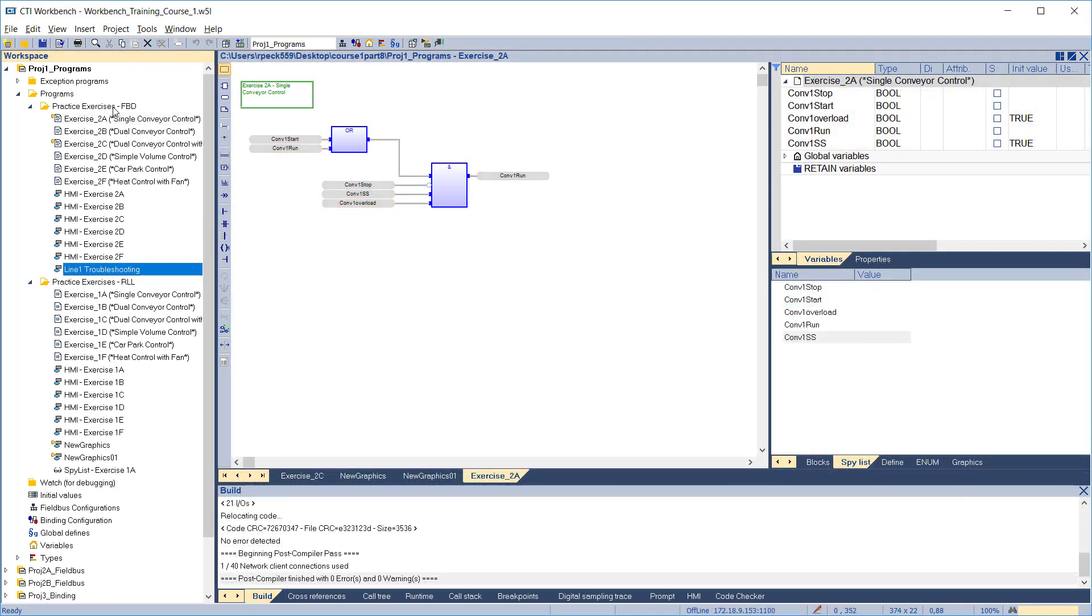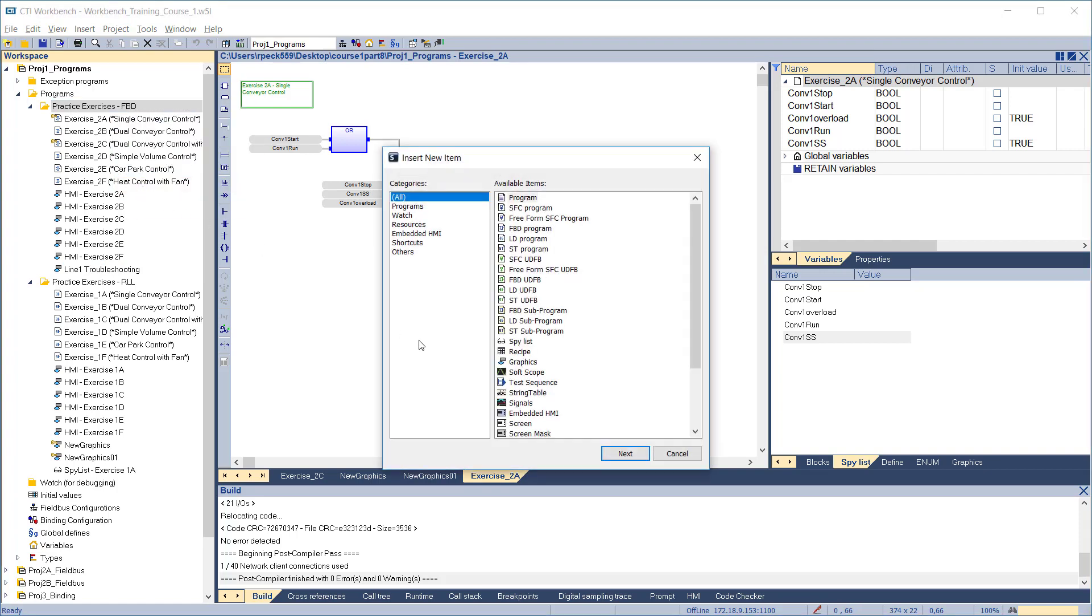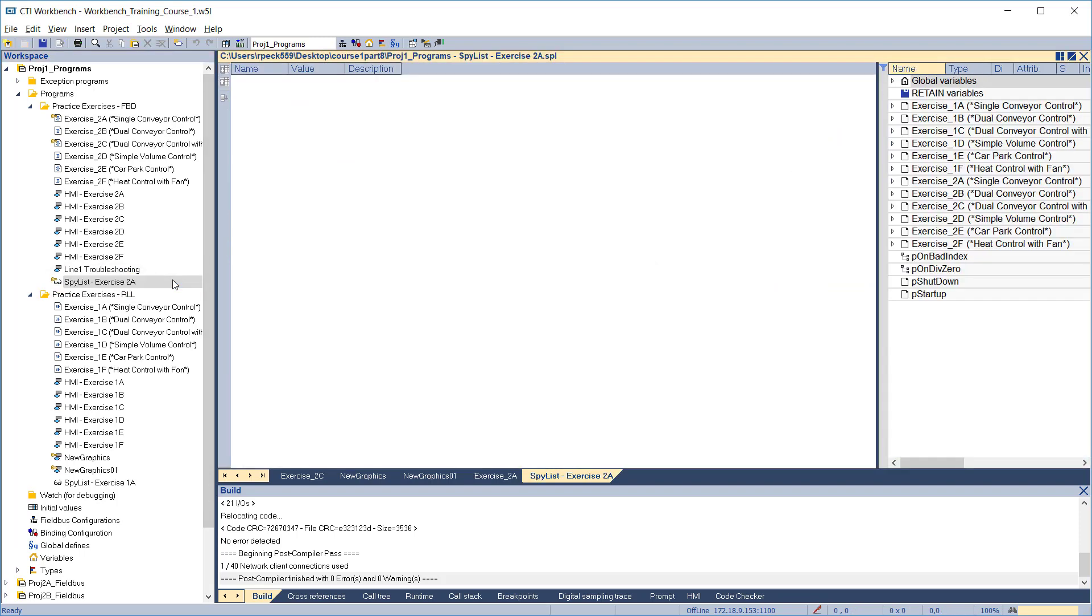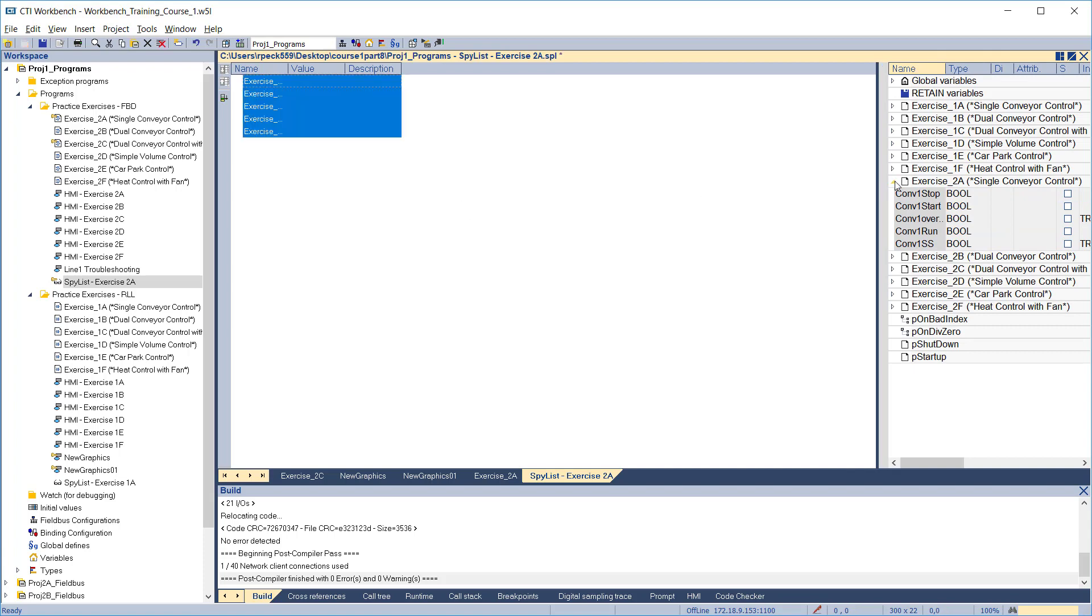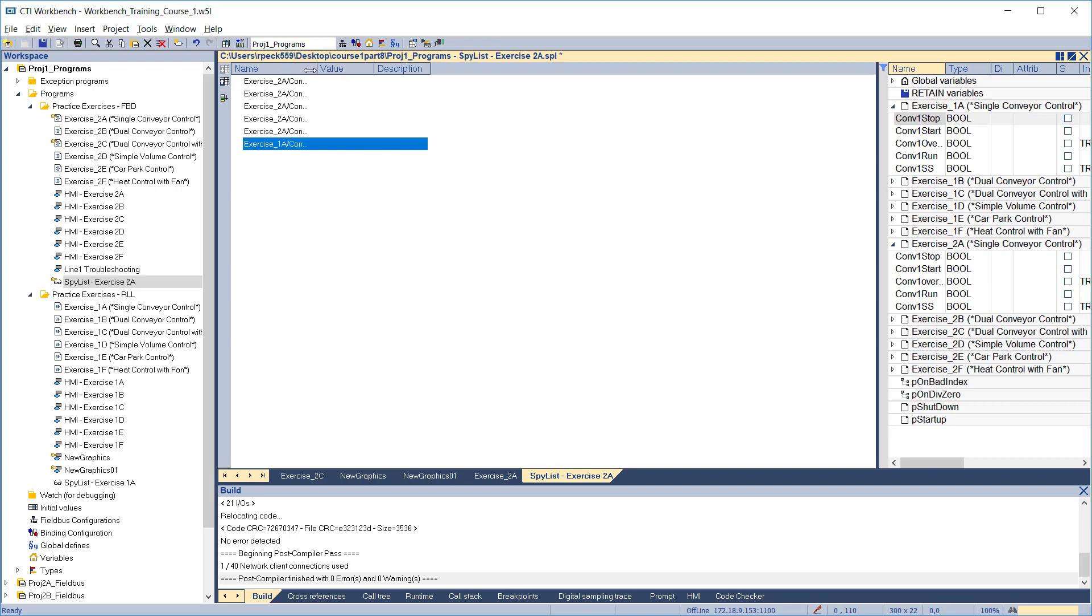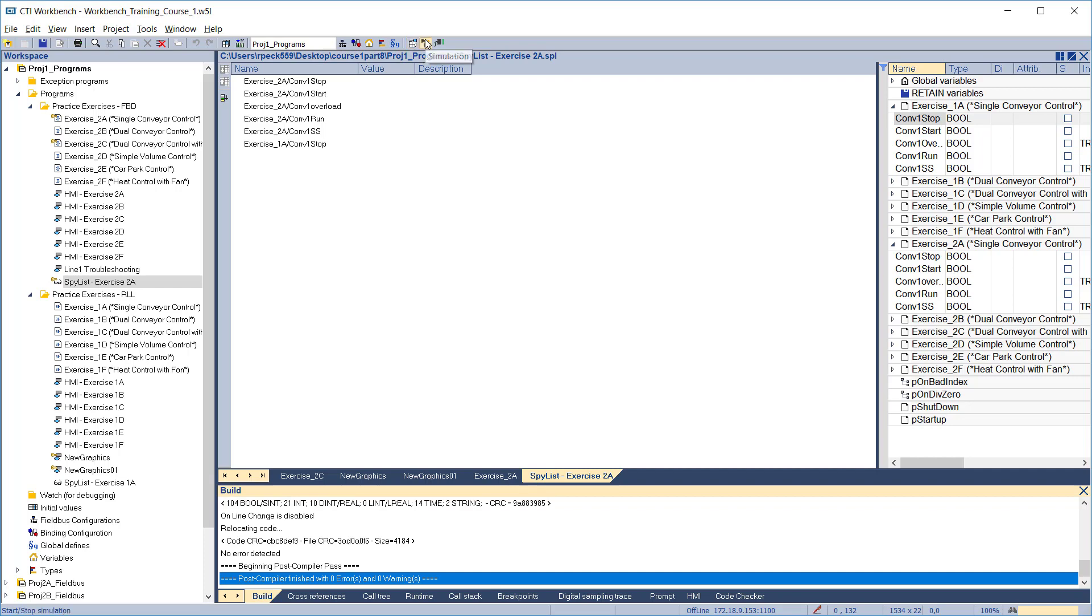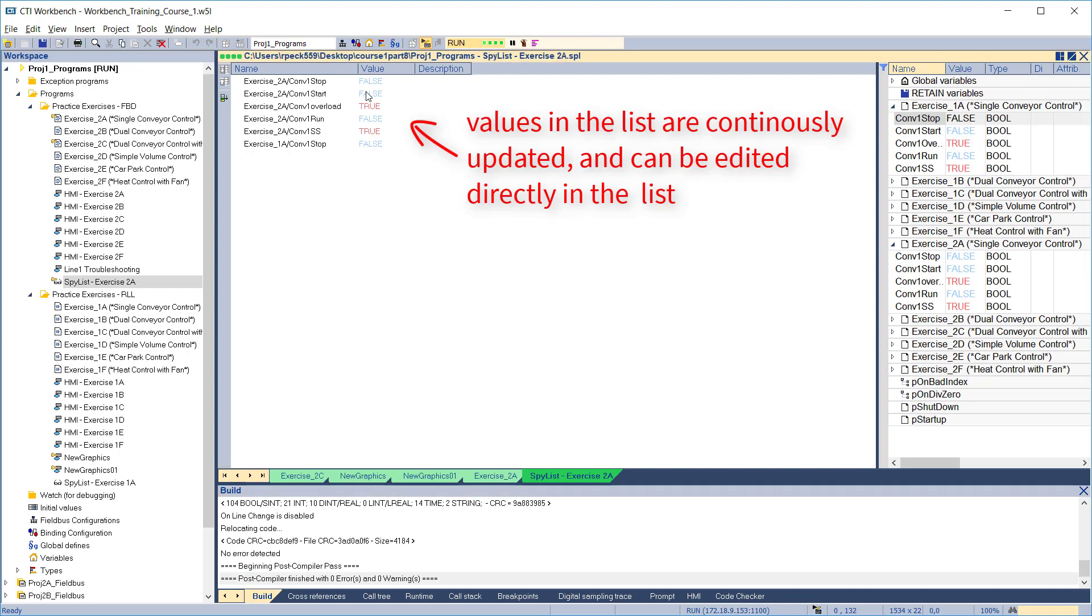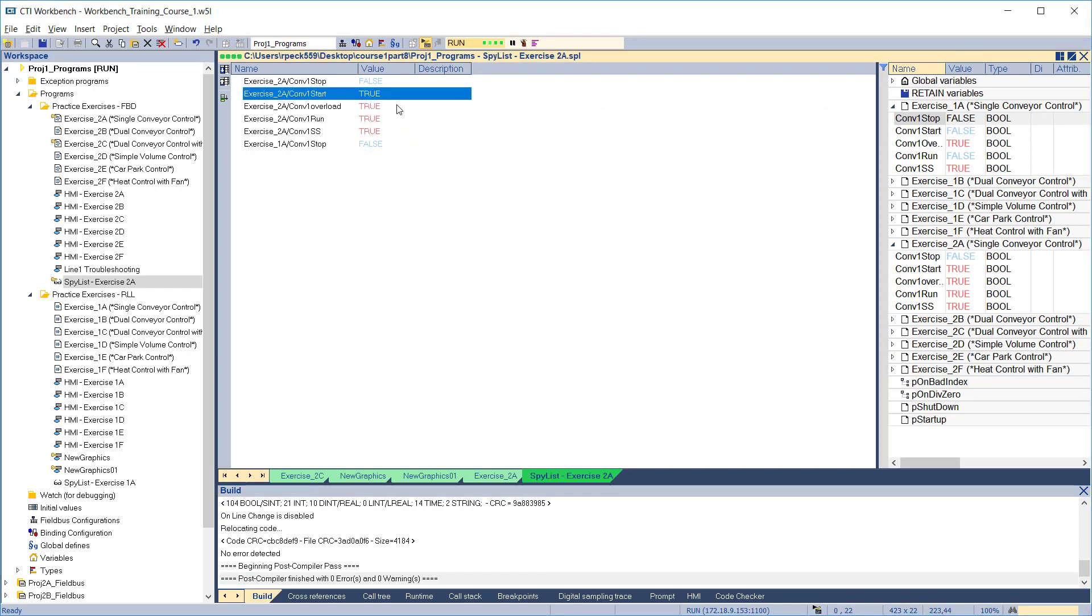You can also create spy lists which are stored in the workspace folder hierarchy. You can organize these however you like. To create a spy list, right-click in the folder where you want the spy list to reside, click Insert New Item, then click Spy List from the list of available items. Enter a name for this spy list and a description. Click OK and the spy list is created. Double-click the spy list to open it for editing. Then just drag the desired variables into the spy list from the variables pane. During runtime, these values are continuously updated and the values can be edited by double-clicking to open the variable editing dialog.